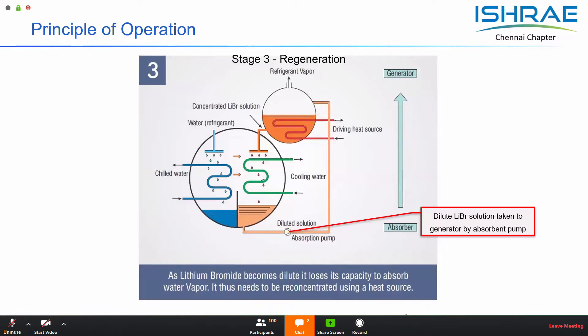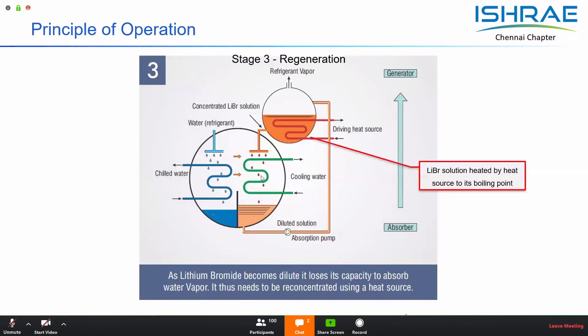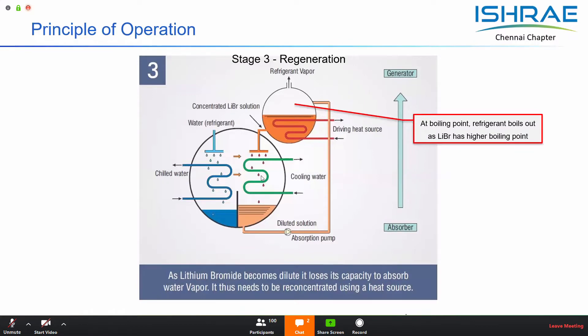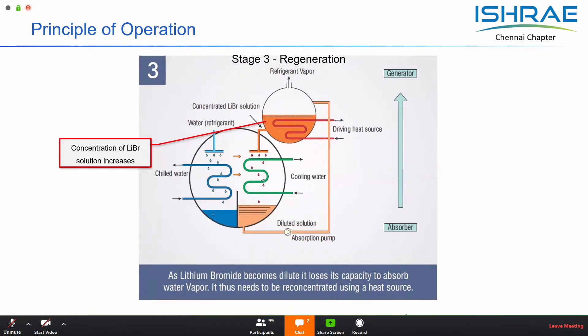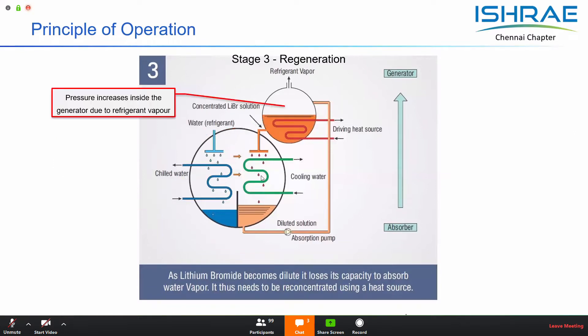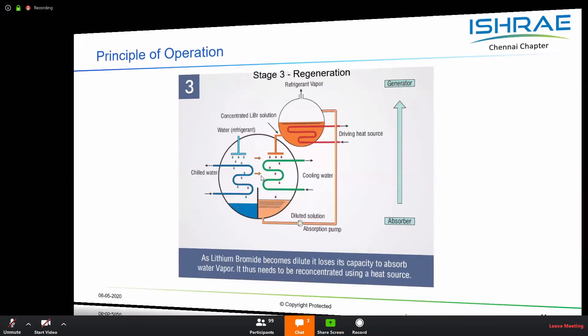To continue this process, we have to separate the refrigerant from the lithium bromide. The lean solution is pumped into the generator section, where the heat source is used to heat the lithium bromide solution to its boiling point. As the temperature rises and reaches the boiling point, the refrigerant inside the lithium bromide solution evaporates because of the difference in boiling points of the salt and refrigerant. The refrigerant vapor is produced, and the high-concentration lithium bromide solution can be put back into the absorber to continue the absorption process.